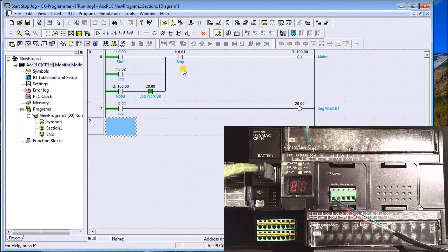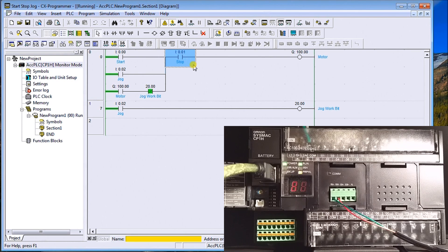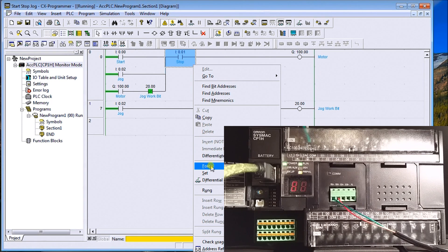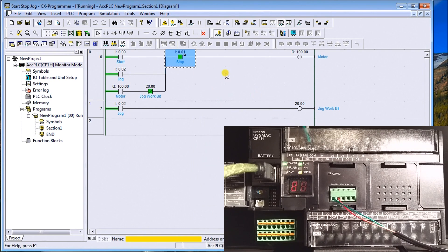Now that we're in monitor mode, we can force I/O on and off. Here's my stop contact — normally it would be wired normally-closed into your input, but I don't have that wired up. To force it on, we put our cursor over that contact, right-click, and go to Force > On. That bit is now energized — shown in green — and you see a little lock symbol beside the contact, meaning it is forced on.